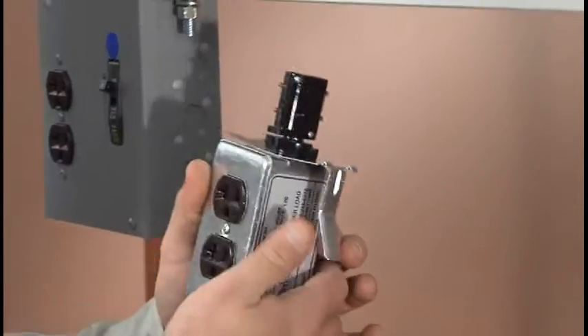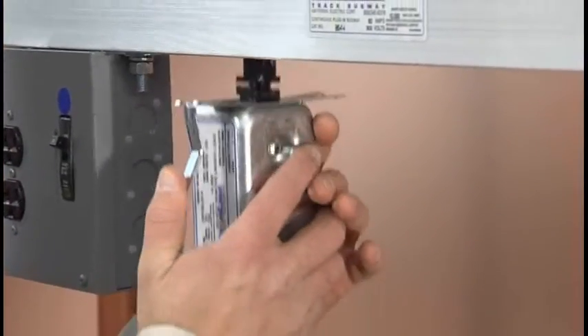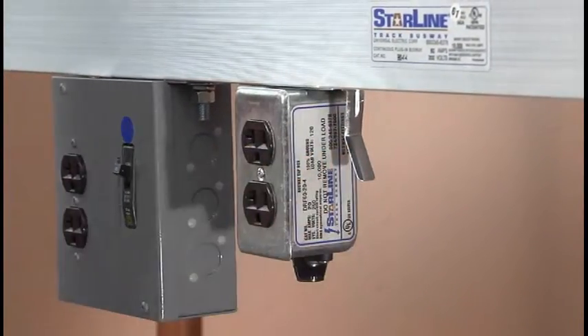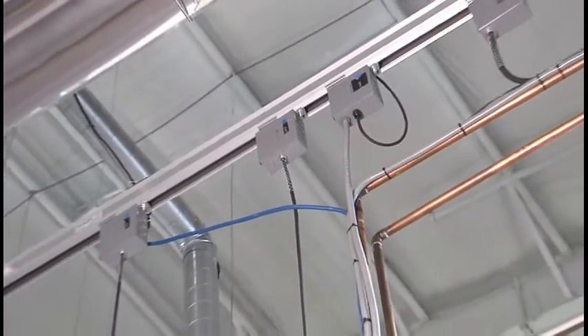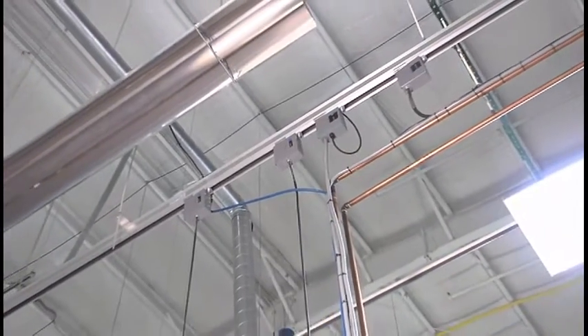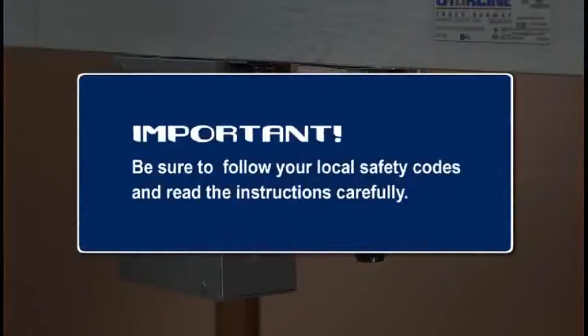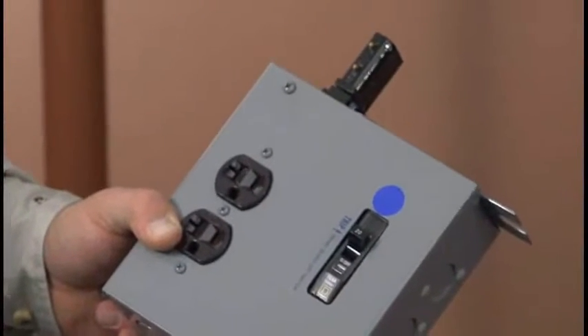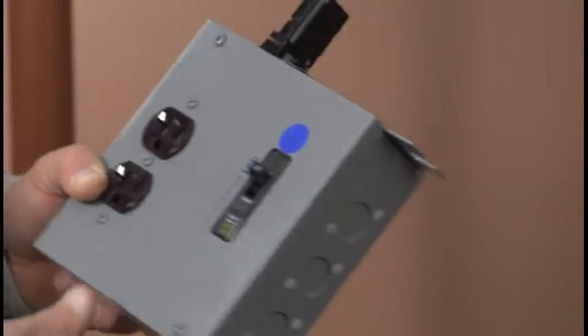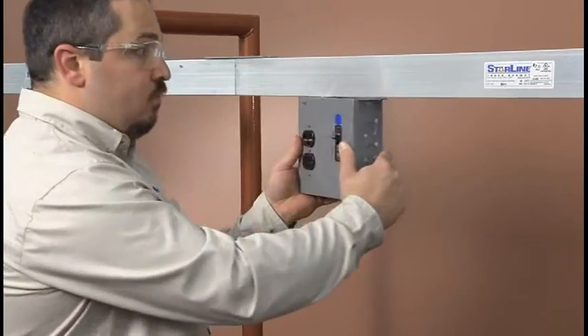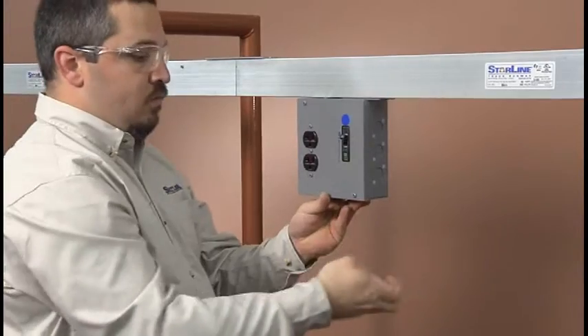Starline Track Busway offers a wide variety of plug-in units that fit any need. The busway can be tapped instantly at any location, saving you time and labor costs. First, be sure to follow any safety codes that may apply. Make sure that the label on the plug-in unit is on the same side as the polarizing strip on the busway. Then, just insert, twist, and install the hanger bolt.